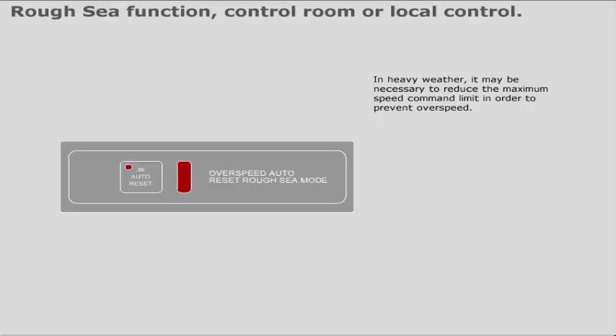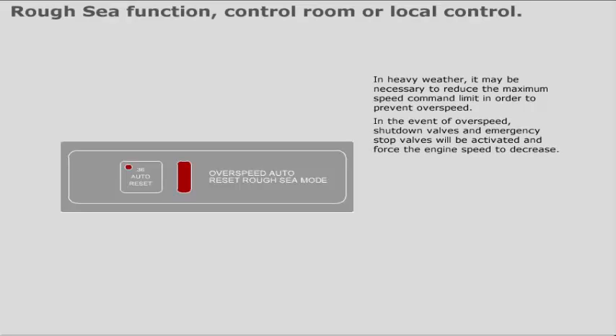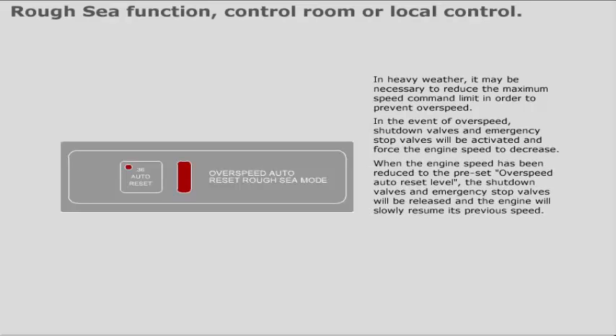In heavy weather it may be necessary to reduce the maximum speed command limit in order to prevent overspeed. In the event of overspeed, shutdown valves and emergency stop valves will be activated and force the engine speed to decrease. When the engine speed has been reduced to the preset overspeed auto reset level, the shutdown valves and emergency stop valves will be released and the engine will slowly resume its previous speed.